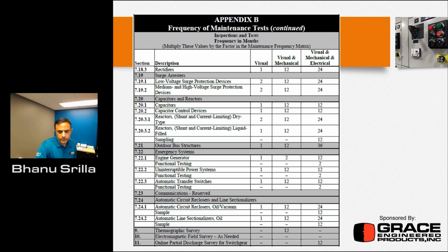Please note that ANSI torque specs for bolt sizes for steel, that is correct. I did not put all types of bolts and different configurations. I just gave you a sample, so this is in no way a complete, exhaustive list of everything. You need to go and look at ANSI NETA 2019 or NFPA 70B to get the torque values across the board, so you can get exactly what you're looking for your equipment. What I presented on the slides is just a snip to give you a feel for what exactly these tables look like.